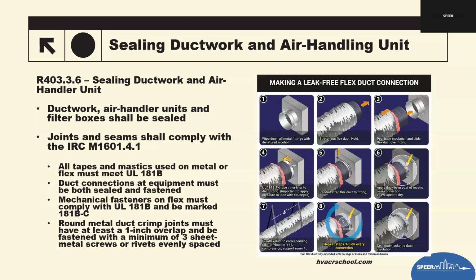And if we're doing anything with round metal duct, basically all the joints need to be crimped, must have at least a 1-inch overlap, and be fastened with a minimum of 3 sheet metal screws or rivets evenly spaced around the joint.